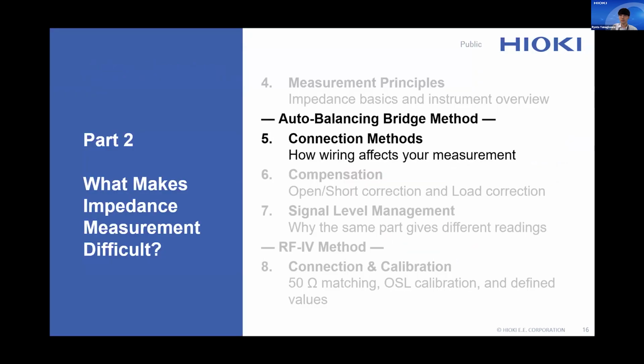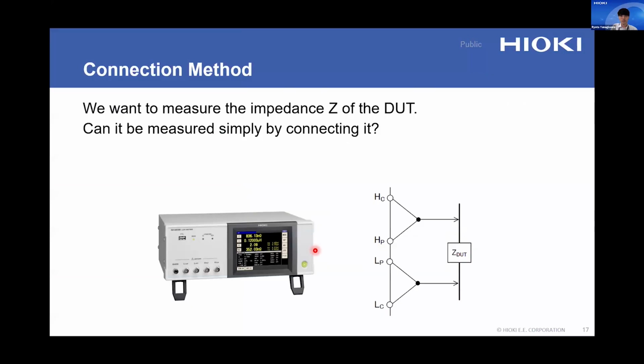Okay, now let's talk about connection method. This is where many measurement errors originate before you even press the start button. The way you connect your device under test, called the DUT, has a direct impact on what you actually measure. The meter will give you a measurement value, but obtaining an accurate result requires some know-how. One important aspect of this know-how is the wiring method.